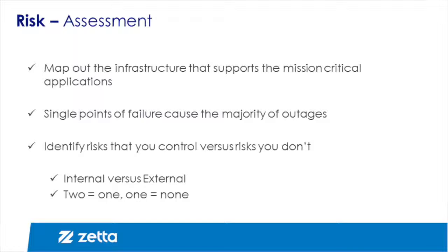When we talked earlier about where Zetta was having problems with one of our hosting companies, we had a situation where we were losing power from the hosting company from their breakers at their power distribution unit. By setting Zetta's infrastructure up so we have a power source that goes to two different PDUs, even though they had a problem, it didn't bring down Zetta.